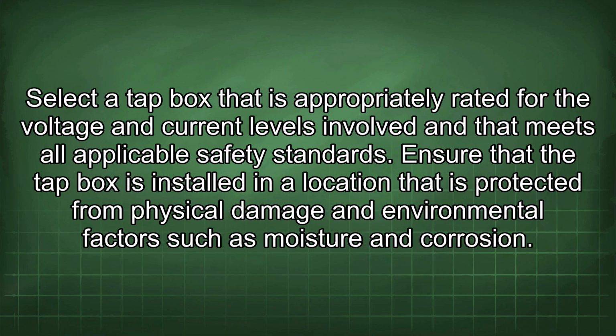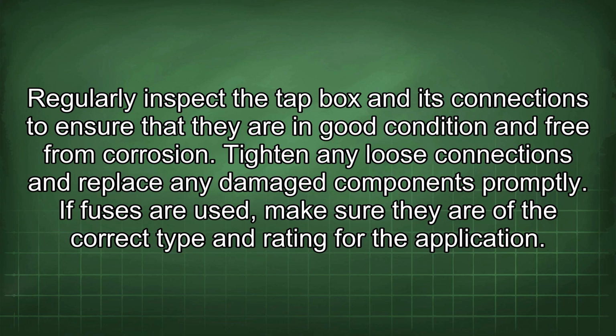Select a tap box that is appropriately rated for the voltage and current levels involved and that meets all applicable safety standards. Ensure that the tap box is installed in a location that is protected from physical damage and environmental factors such as moisture and corrosion. Regularly inspect the tap box and its connections to ensure that they are in good condition and free from corrosion. Tighten any loose connections and replace any damaged components promptly.